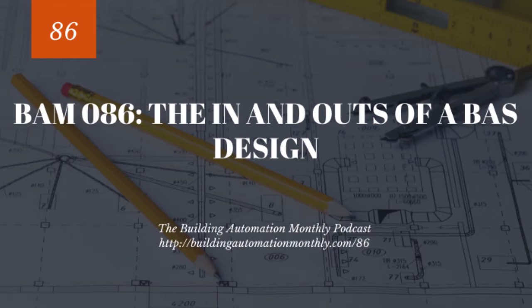But if for some reason you are taking SDs and creating a design and submitting that design, which I've seen happen before several times, then you could have a very inaccurate design to the point of like, hey, this schematic design has a central plant, and now all of a sudden it has rooftops with DX coils instead of hydronic units anymore. And all of your design is pretty much scrap. So it's really important to understand what drawings you're working with, what percent complete, and then what phase they're in.